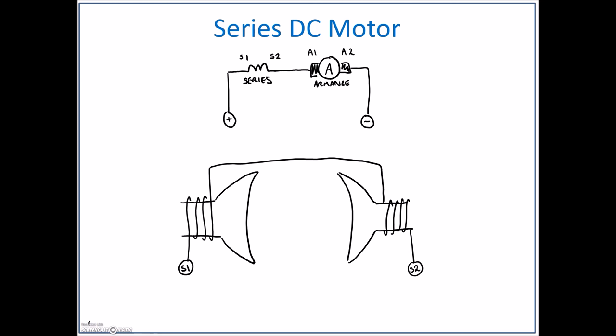The inside electromagnet is called the armature. The armature is that rotating electromagnet where we've got all these conductors, or bars, depending on the size of the DC motor, all the way around. Each of those goes into the commutator. Commutator are the bars of copper that allow us to get current to flow on that rotating electromagnet.